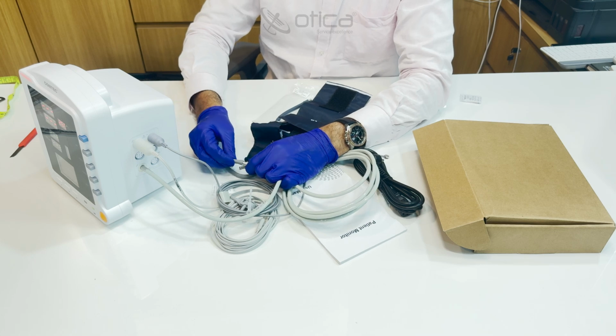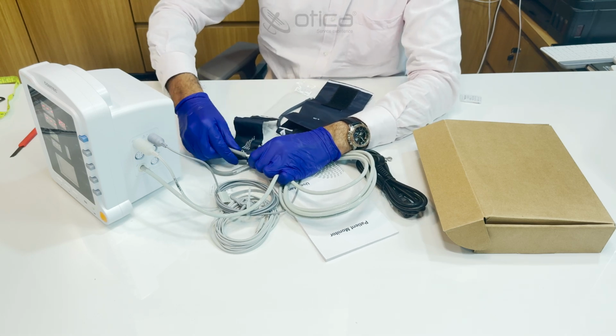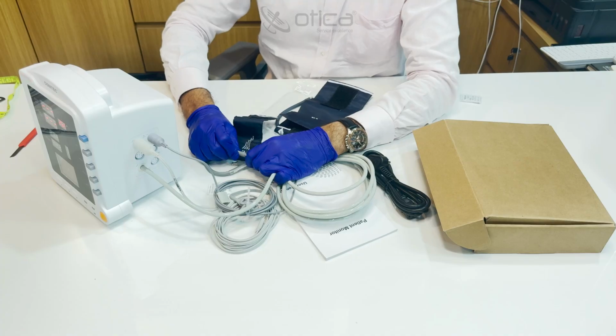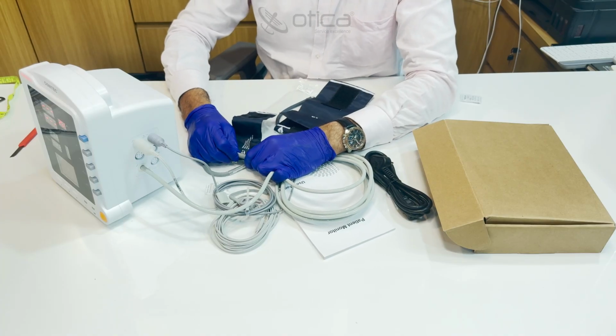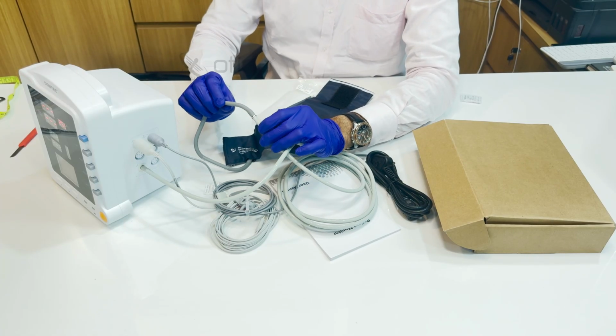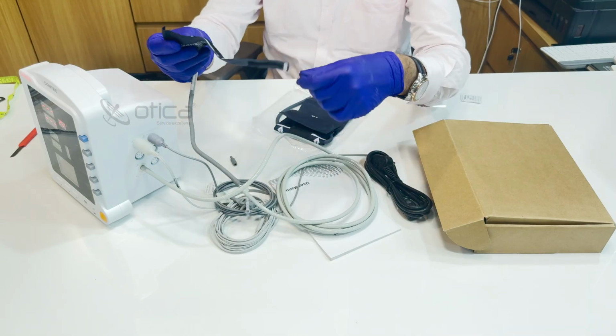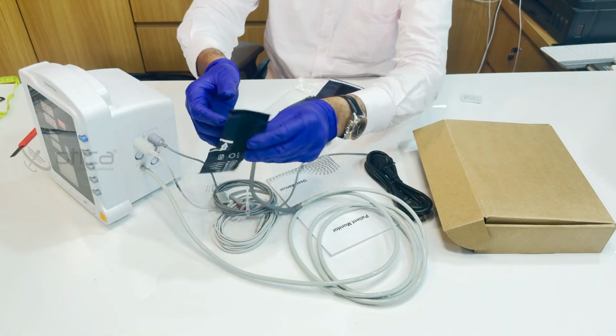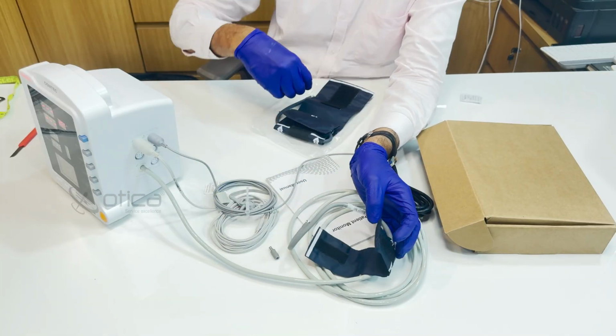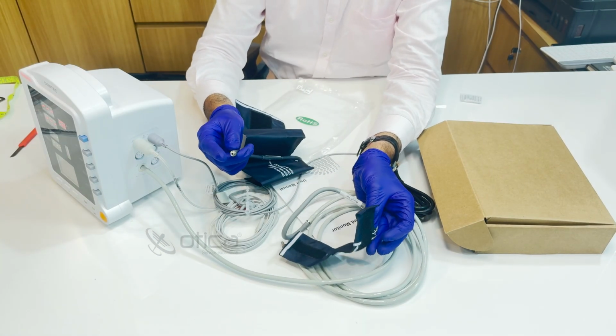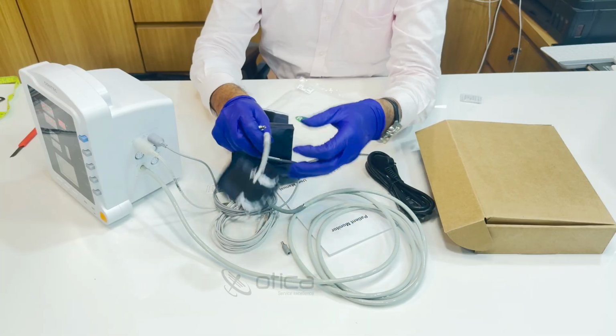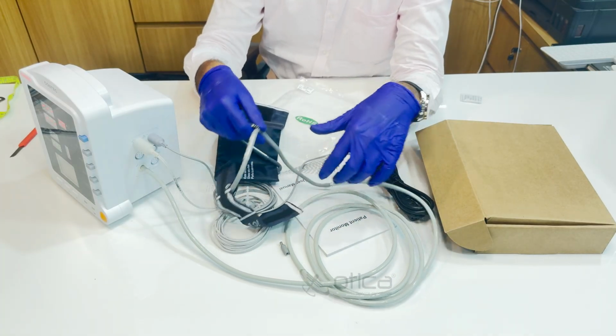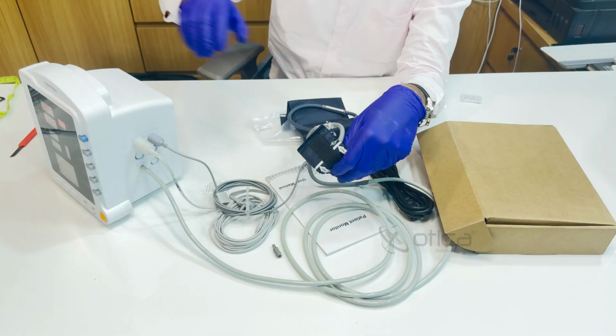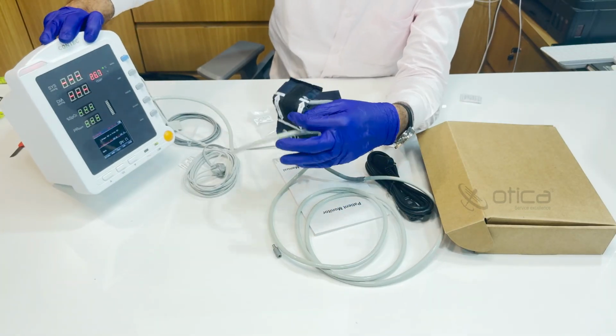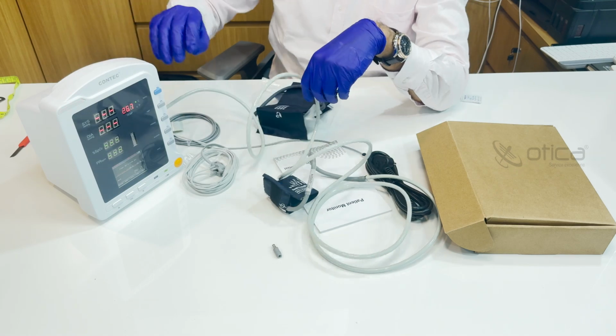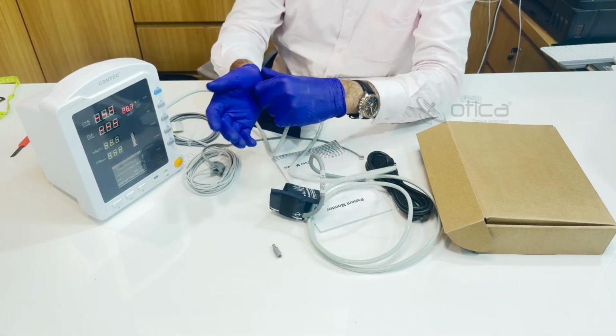Make sure you are making a proper and thorough connection between the tube and the connector. Then it will work properly, otherwise there will be some error. You have to make sure to remove this old connector from the cuff and connect the male connector directly into the silicone tube.